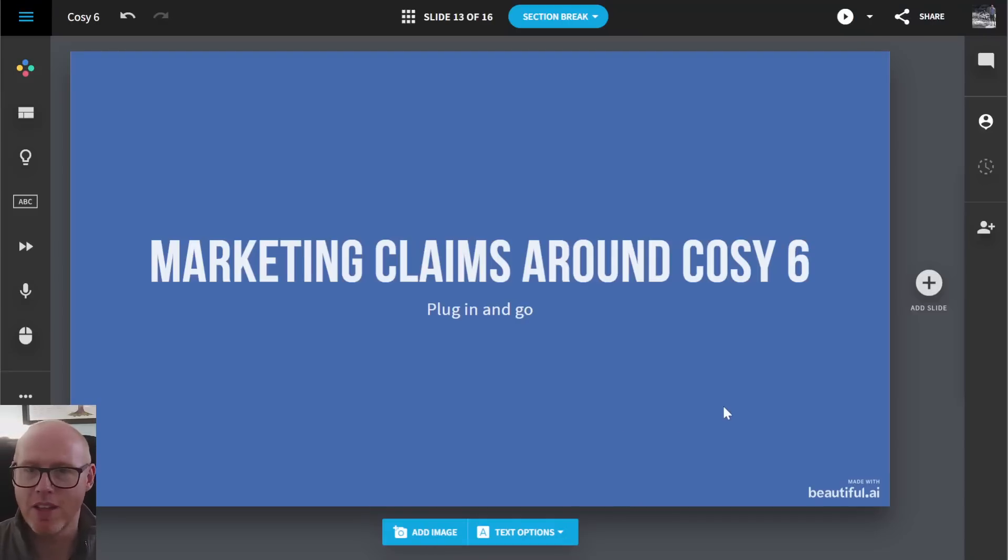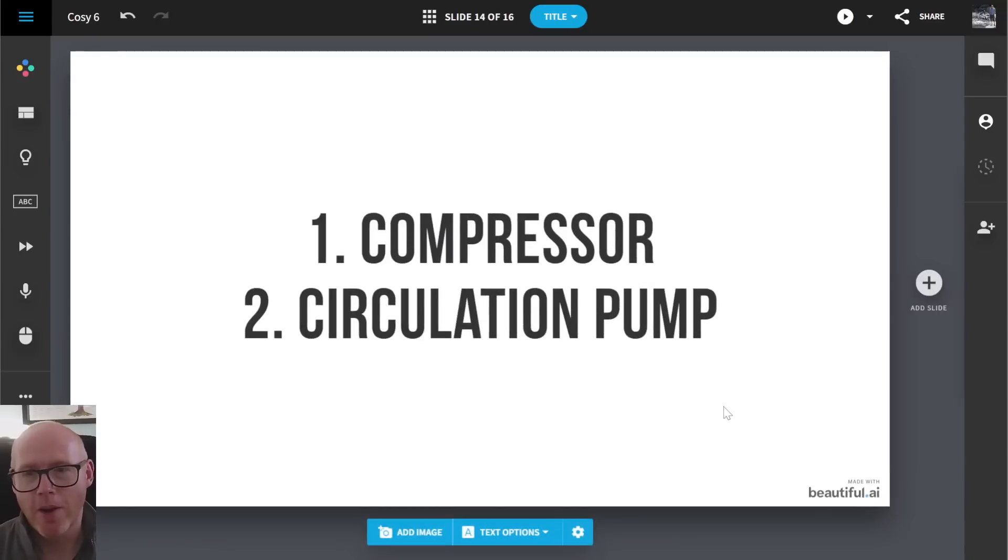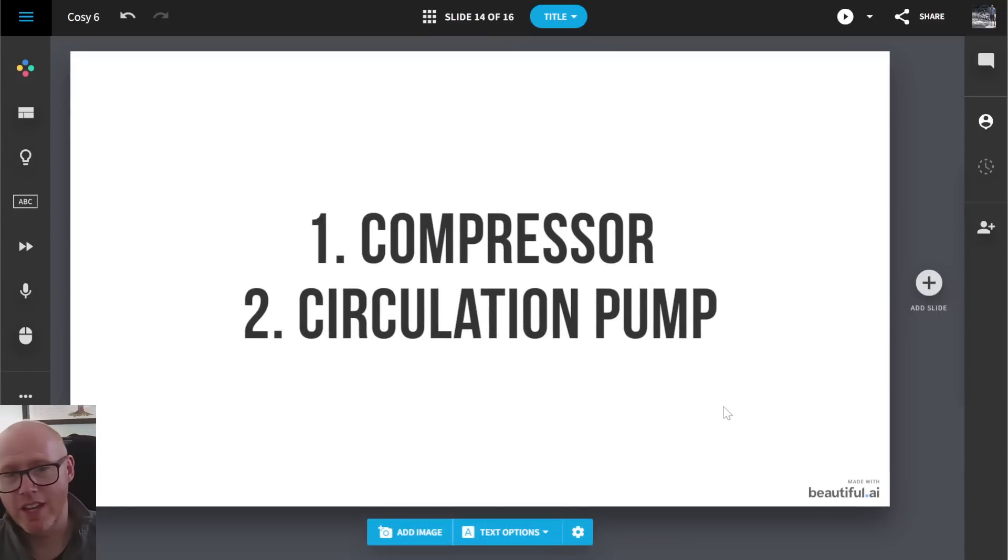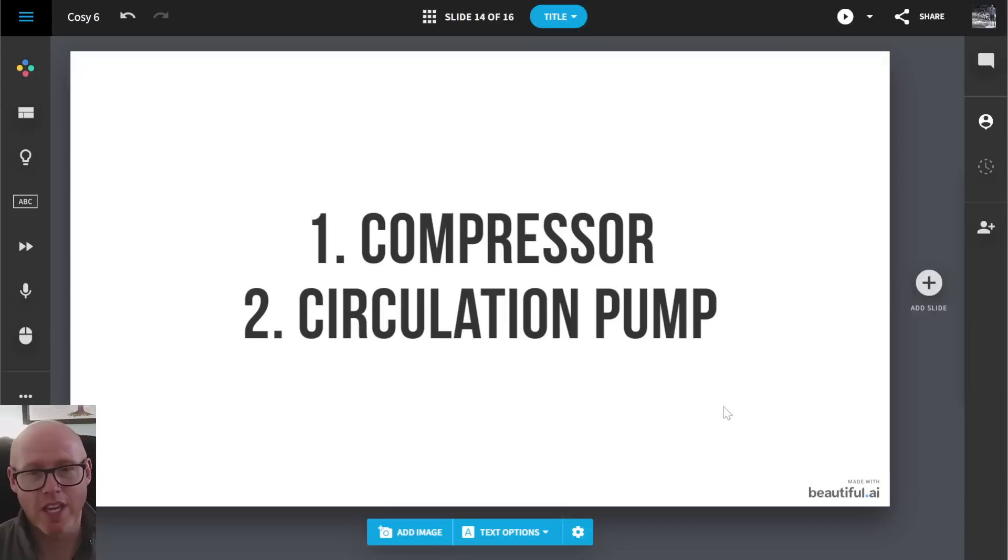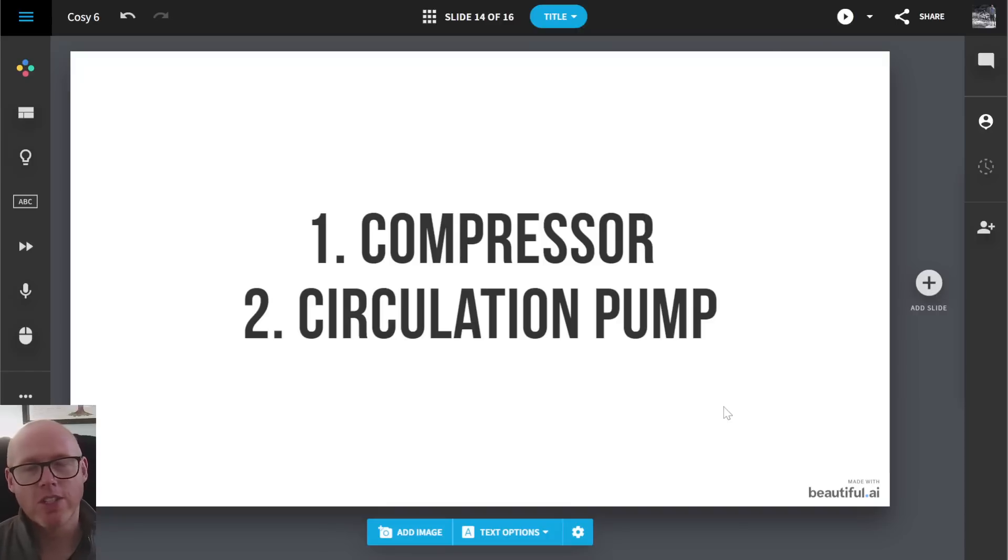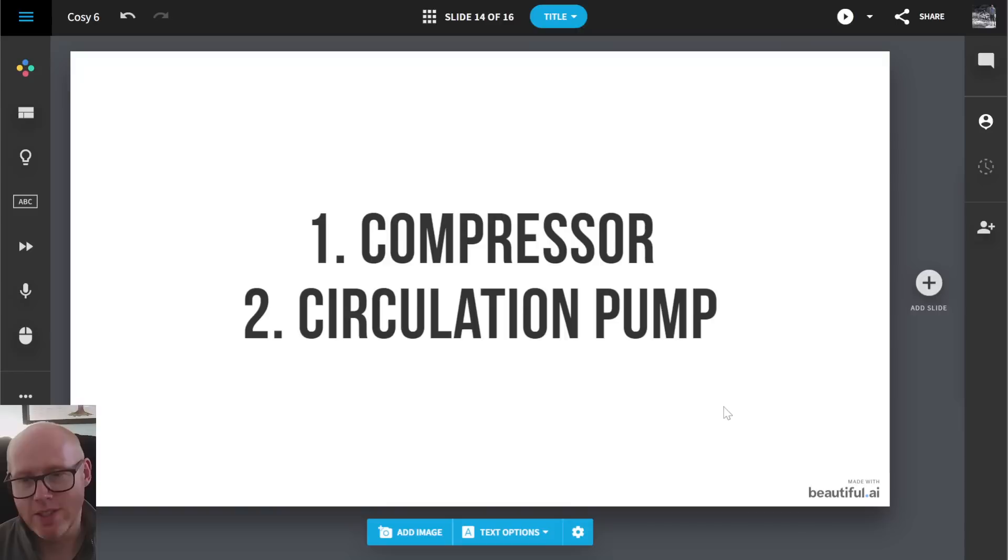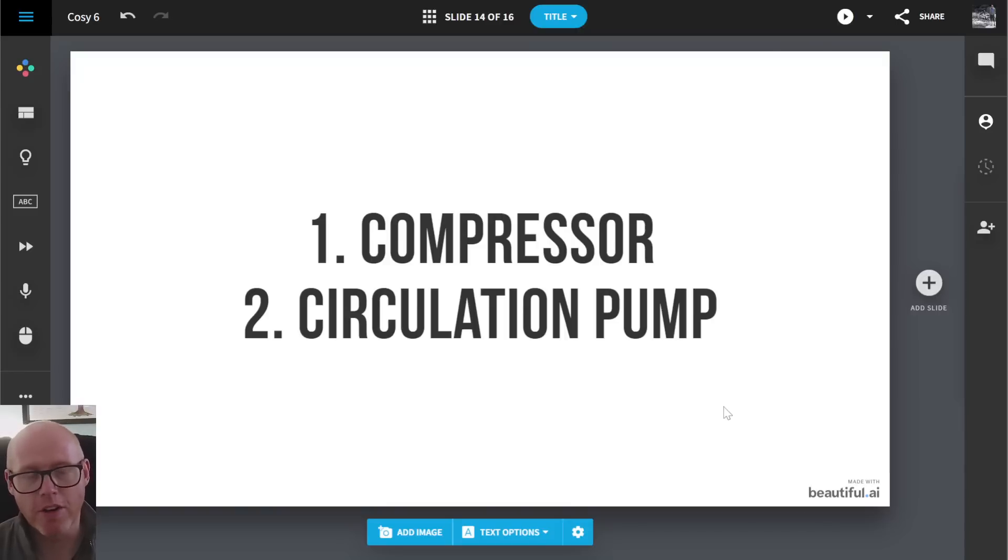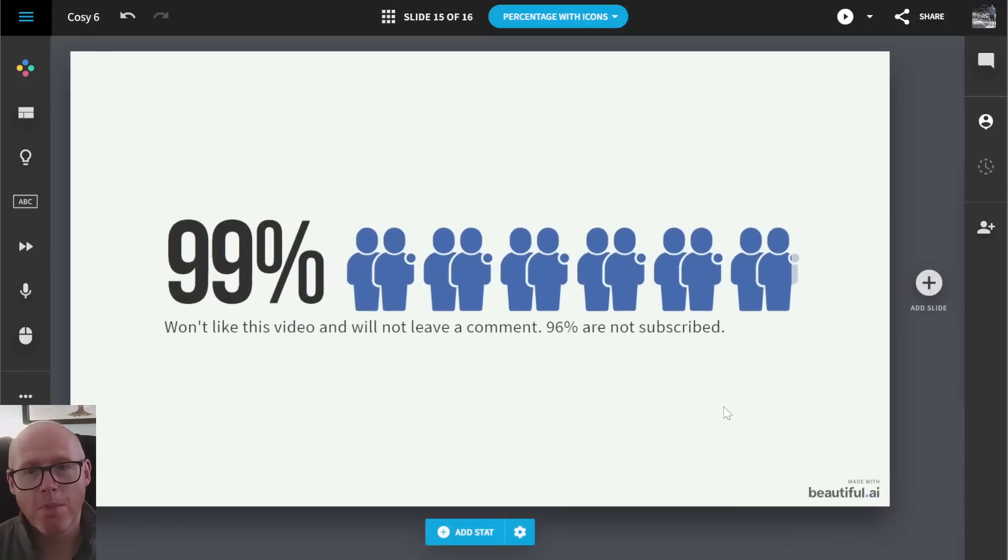So we've learned about the compressor. It can clearly only modulate. Even these inverter driven compressors, they can only modulate down typically to 30-ish percent of their maximum output. So if it's rated at 6 kilowatts, then maybe it can modulate down just below 2 kilowatts. And we've learned that the circulation pump is not enough for a long primary run and 10 mil microbore. A lot of people have been told that the Cosy 6 can't be installed on microbore. And I wonder if this is an issue to do with it.